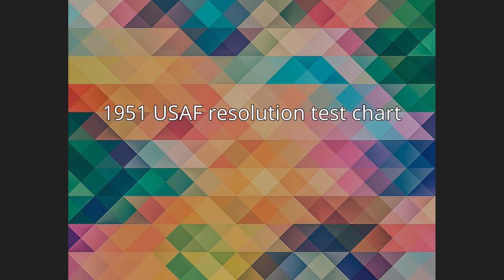It is widely used in optical engineering laboratory work to analyze and validate imaging systems such as microscopes, cameras, and image scanners. The full standard pattern consists of 9 groups, with each group consisting of 6 elements. Thus, there are 54 target elements provided in the full series. Each element consists of 3 bars which form a minimal Ronchi ruling.